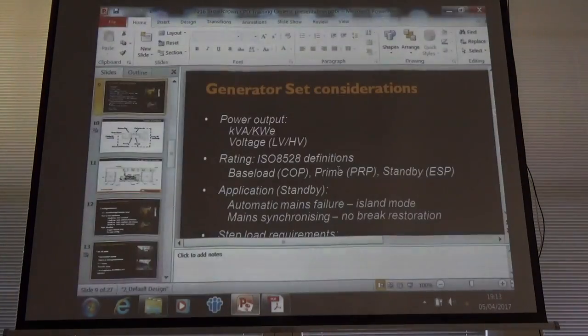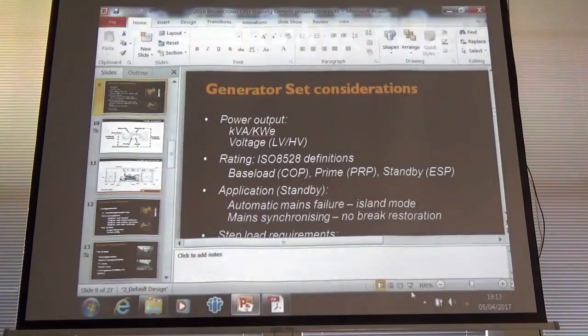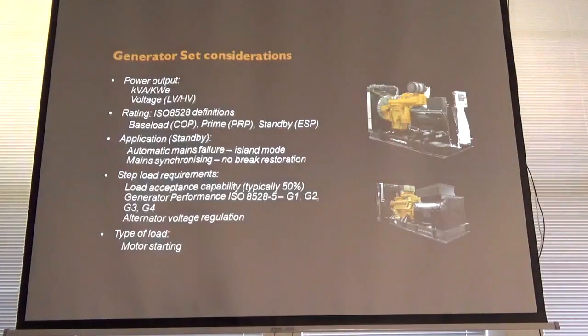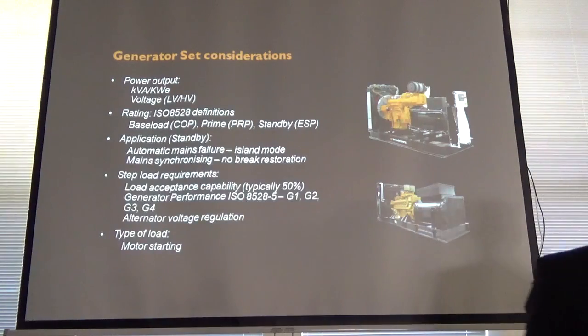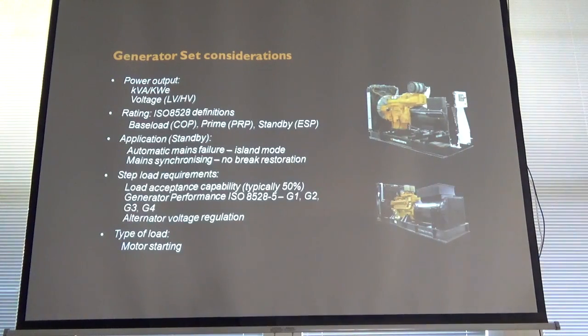So, go back to the G tolerances. It's probably best for me to highlight that. All I would say to you is always default to G2, unless the sensitivity of the equipment dictates otherwise. G3 is 15% voltage dip, 7% frequency dip, and G4 is you tell me what you want over and above that. That's how it gets.